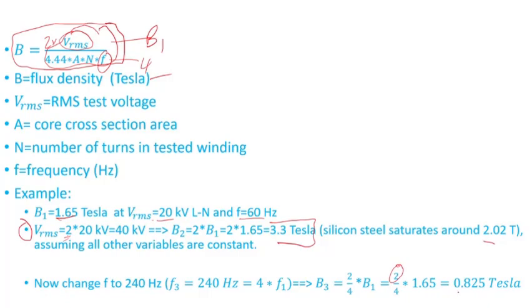...the flux density was very low because I increased the frequency. So the frequency increase compensated for the voltage increase. So 0.825 Tesla is way less than 2.02 Tesla.